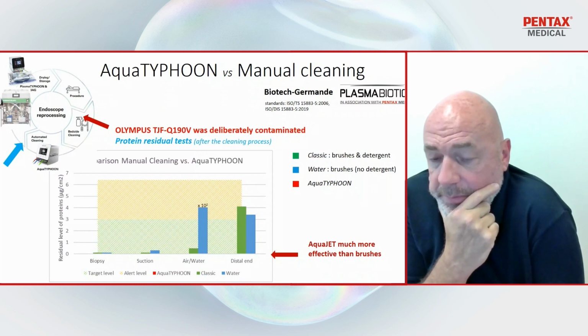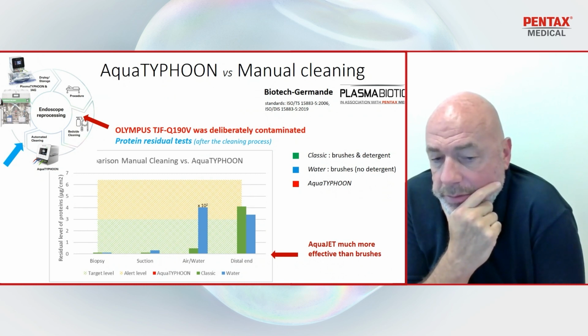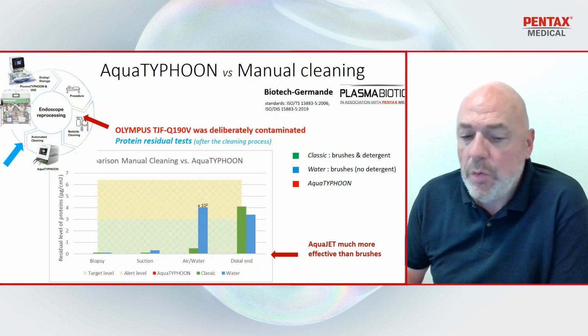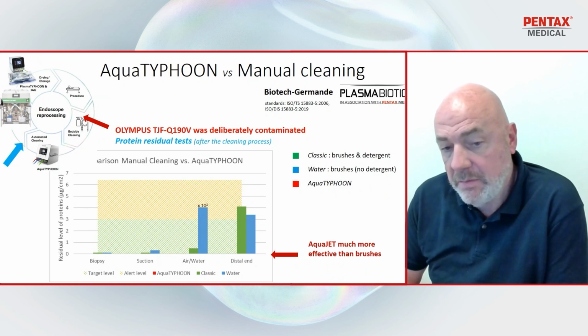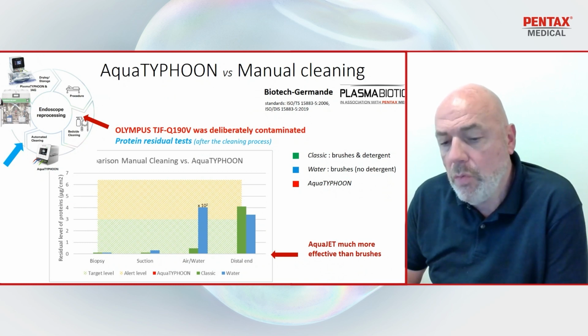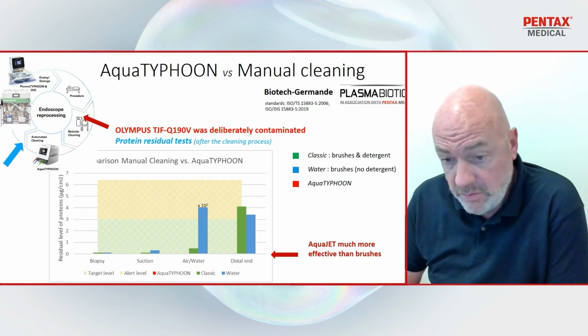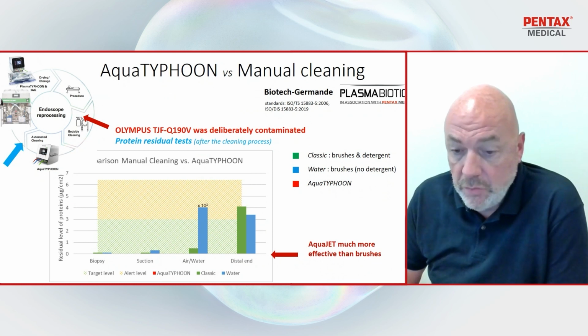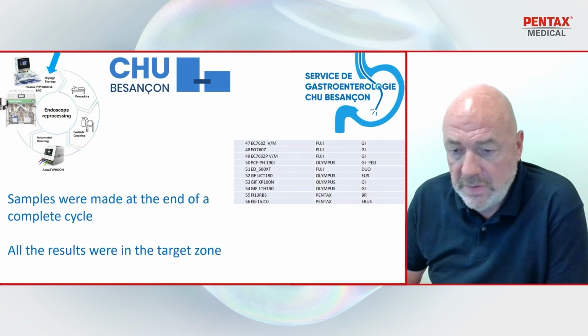So what is the result? We need more data. The first study is from Biotech Germany, which is a big factory. They deliberately contaminated a duodenoscope from Olympus. They started the Aqua Typhoon cycle, and just after that, before the automatic cleansing and disinfection, they took some samples to look for protein residual. As you can see, after classic manual brushes and detergent, in green, the result was very bad. After water brushes without detergent, the result is very, very bad. And after Aqua Typhoon, you can't see the result because it's very small.